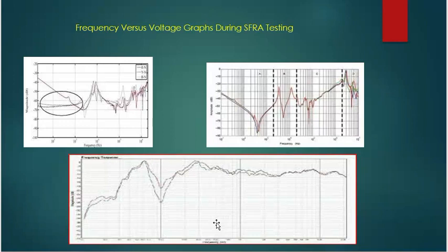But after transportation or a heavy short circuit fault, transient switching fault or lightning impulse voltages, we have to do this same test and superimpose this result on the previous value to see if any deviations are observed. Then we can assess that a mechanical displacement and deformation has occurred in the winding. Two curves are shown here superimposed on each other. One curve is from the factory test value and the other curve is tested at the site, or tested on condition monitoring after 5 or 10 years.